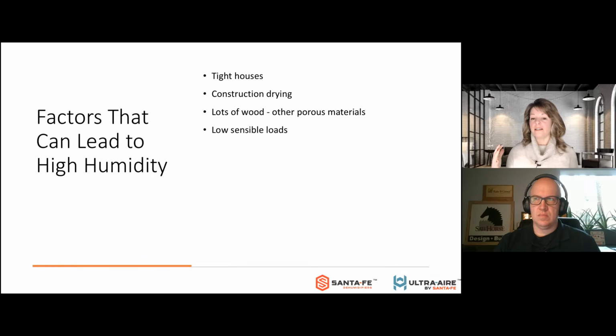And this really pertains to the shoulder seasons. Dew points can be really high outside in our green grass climates in the spring and fall. And there's no reason to be running air conditioning because it's mild outside, 70 to 80 degrees. We don't need a lot of air conditioning, if any, but there's a lot of moisture outside. So we're not running our air conditioner to remove any water.